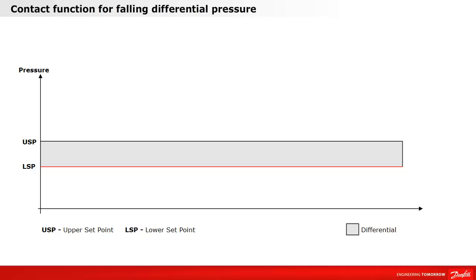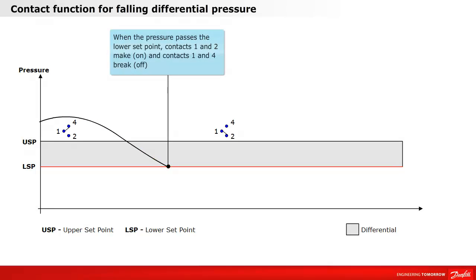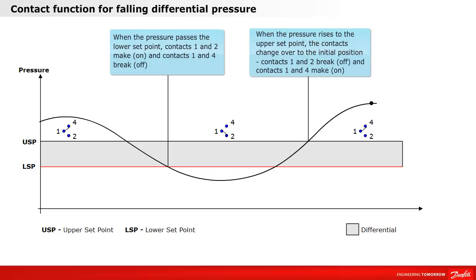Let's take a look at the cutoff for falling differential pressure. When the pressure passes the lower set point, contacts 1 and 2 make and contacts 1 and 4 break. When the pressure rises to the upper set point, the contacts change over to the initial position — contacts 1 and 2 break and contacts 1 and 4 make.